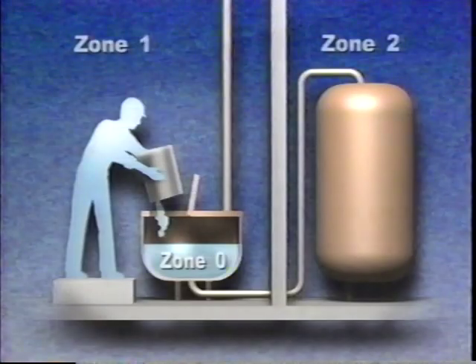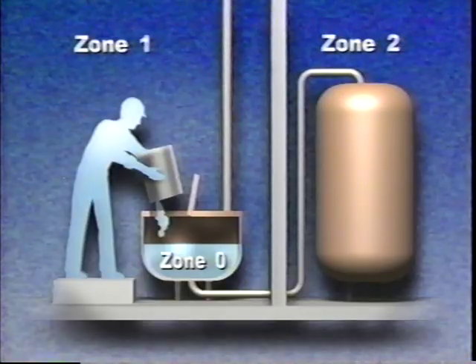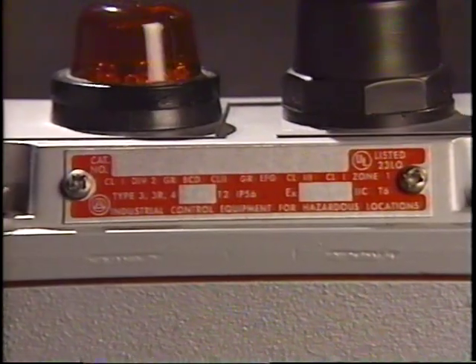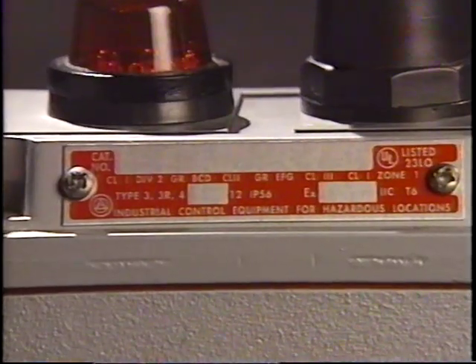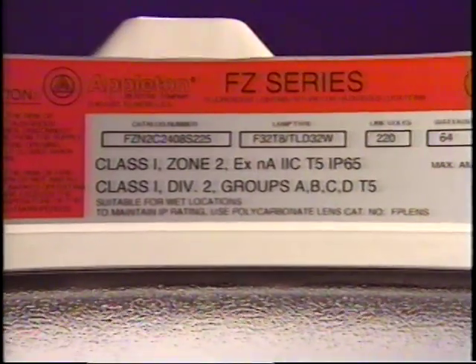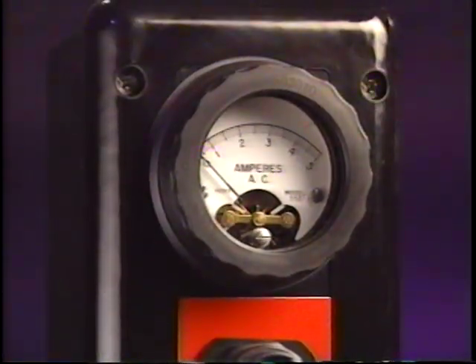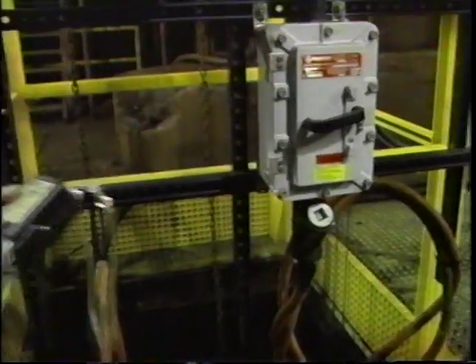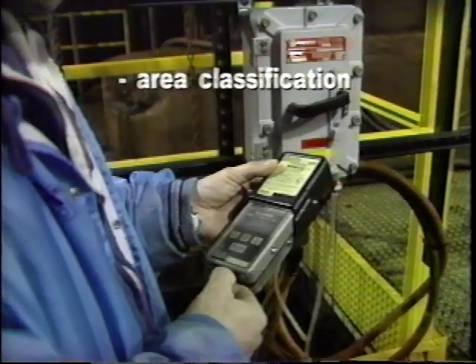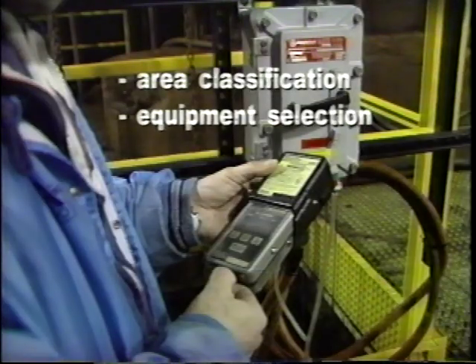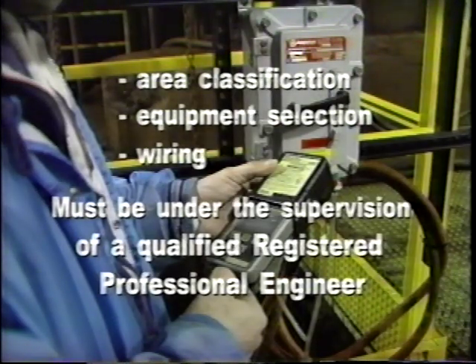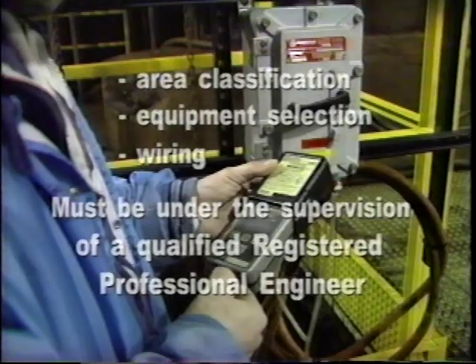New in Article 505 of the 1996 NEC is the option of using the International Electrotechnical Commission, or IEC, Zone Classification System. The zone system classifies equipment according to the type of protection it offers. Equipment approved for use in a zone may be used in a Class 1 area, providing the designer with another option for specifying equipment. When the zone system is used, area classification, equipment selection, and wiring must be under the supervision of a qualified registered professional engineer.